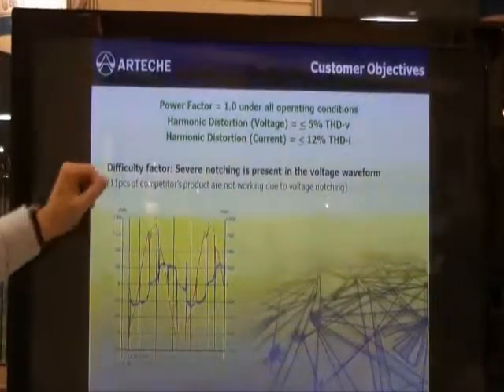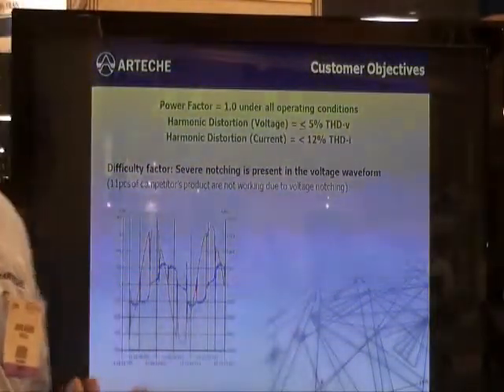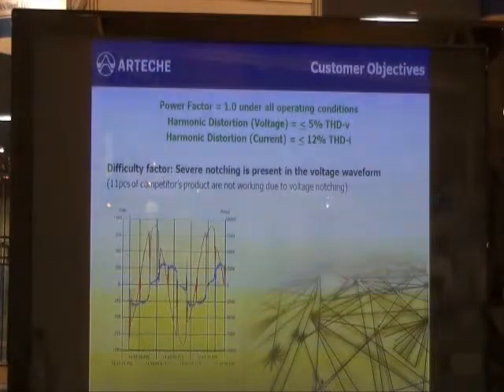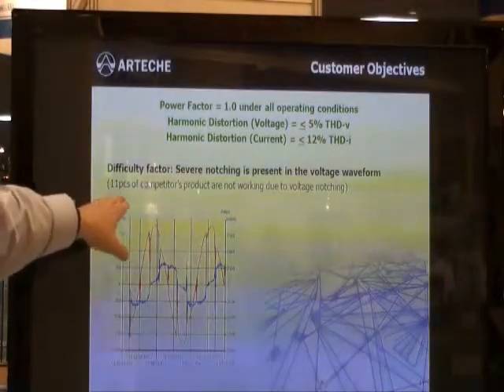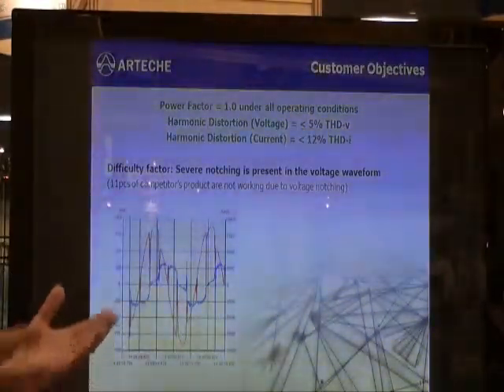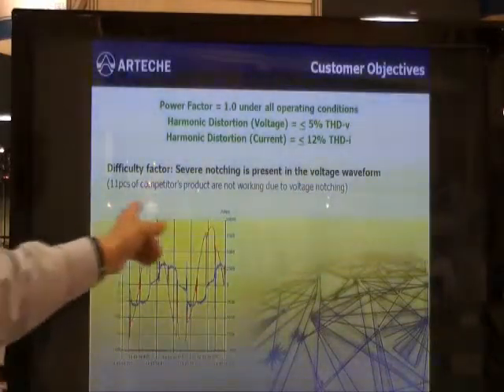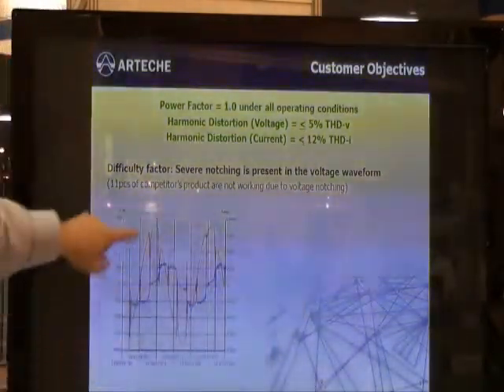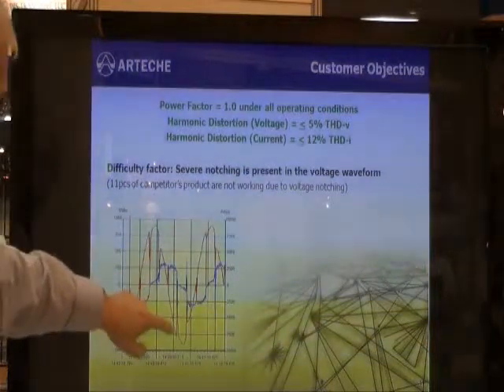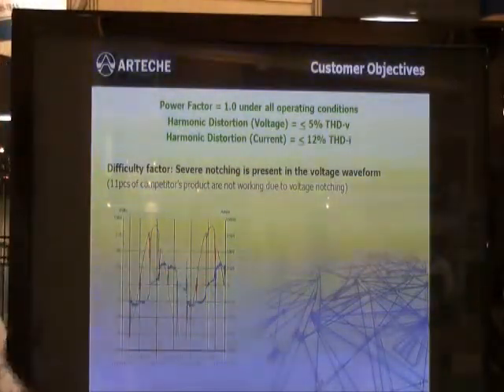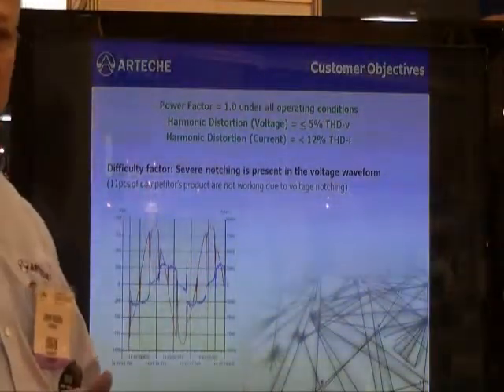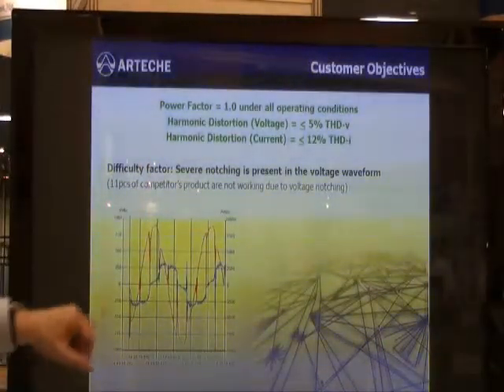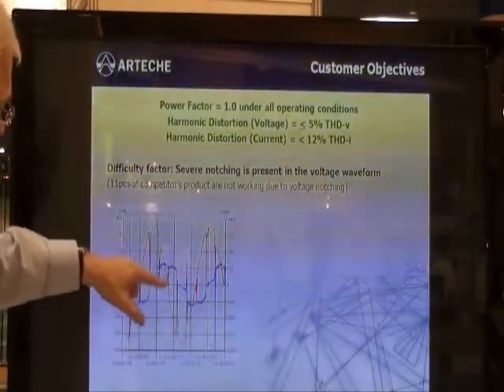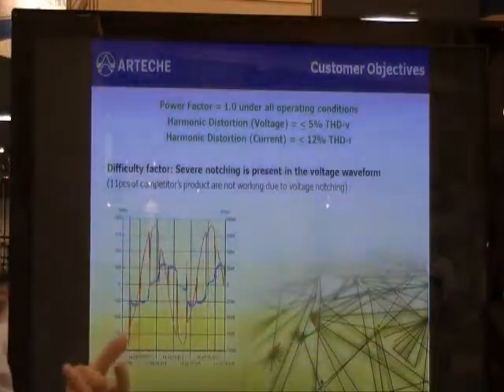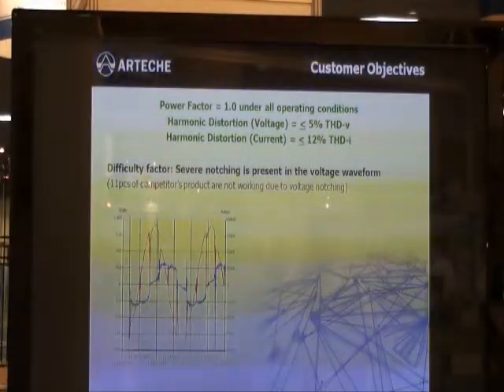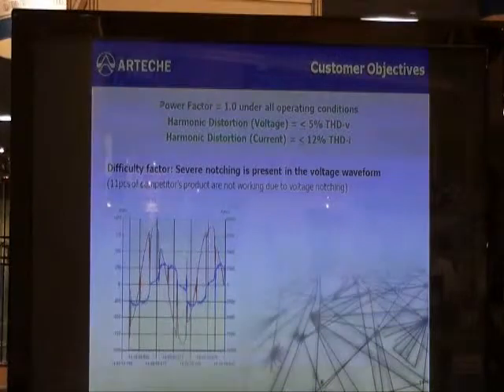Another point of interest is that this has proven over time to be a very difficult application. In fact, the customer in this case had 11 pieces of a competitor's thyristor switch product which were not working, and the reason they were not working was due to these notches in the voltage waveform, which are present because of the SCR motor controls for the DC motors. So these notches represent a false zero cross and were interfering with the other more traditional type thyristor switches.